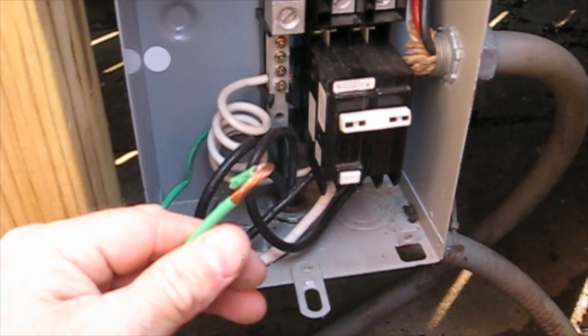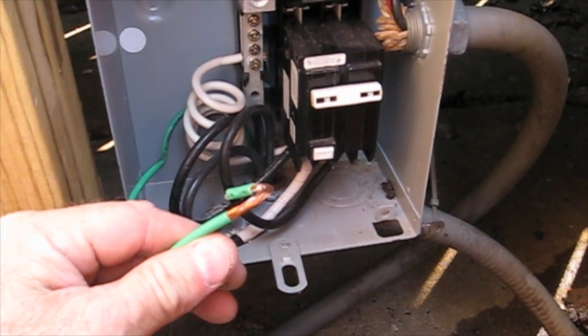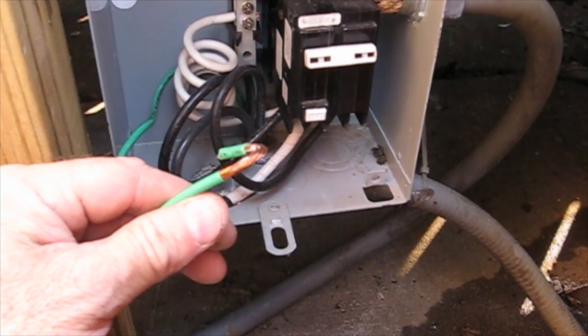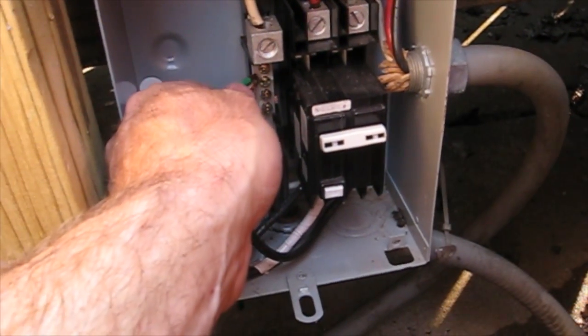And what happens is your GFI is introducing power to ground. With this ground not hooked up, it puts power in the water because your heater and all that stuff is not grounded. Let me touch this and see if it kicks the breaker. I think it will.